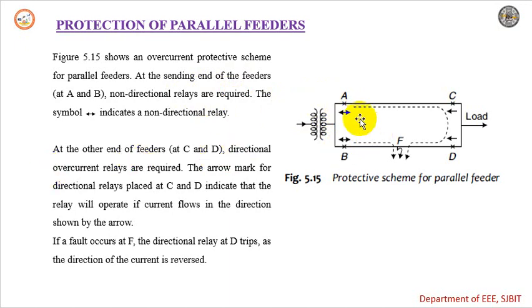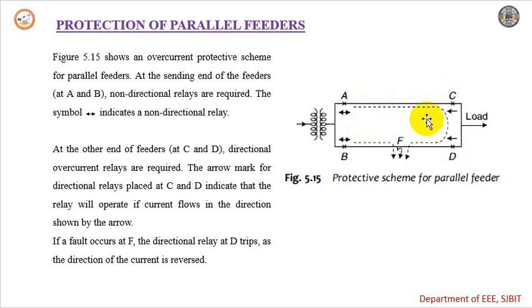At the other end of the feeders, that is C and D locations, directional relays are required. The single arrow indicates it is a directional relay, and the directional relay will operate only when the current is flowing in the arrow direction. So for one feeder, we have one non-directional relay and one directional relay.